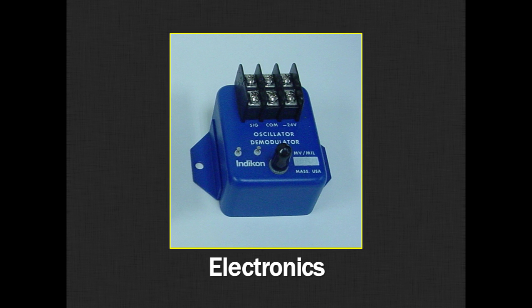So we've talked a little bit about the electronics before and we'll go into a little bit more detail here. Again, the electronics create this oscillation. The oscillation tries to maintain a certain level; permeable material causes that to shrink down. What the electronics do is they take this peak-to-peak signal, this oscillation, and do something called demodulation. So they convert it into an output voltage. So if you have a peak-to-peak signal of a certain amount maybe you'll get a 10 volt output and as this shrinks down because of the permeable materials close to the tip of the probe the output voltage will shrink down. So you take an oscillating signal and convert it into a steady-state signal.